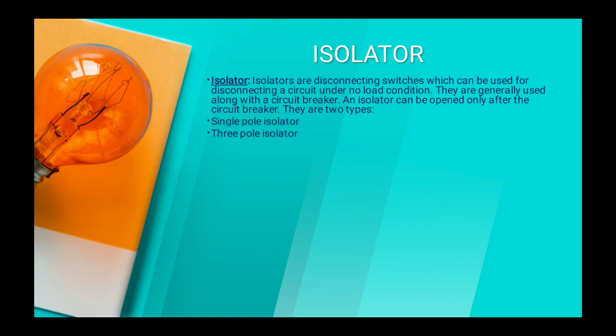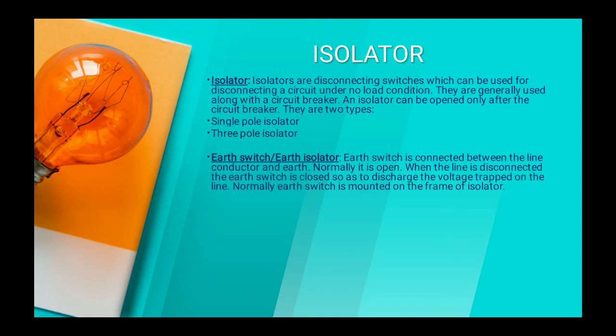There are mainly two types. First, the single pole isolator used in single phase systems; second, the three pole isolator with three contacts used in three phase three wire lines; and third, the earth switch or earth isolator. The earth switch is connected between the line conductor and the earth. Normally it is open. When the line is disconnected, the earth switch is closed to discharge the voltage trapped on the line. Normally the earth switch is mounted on the frame of the isolator, and when the main isolator is disconnected from the line, the earth isolator is closed to discharge the fault current or the trapped voltage on the line.